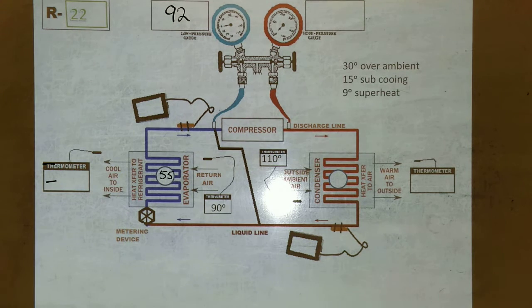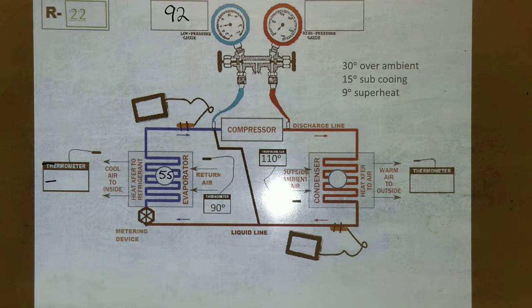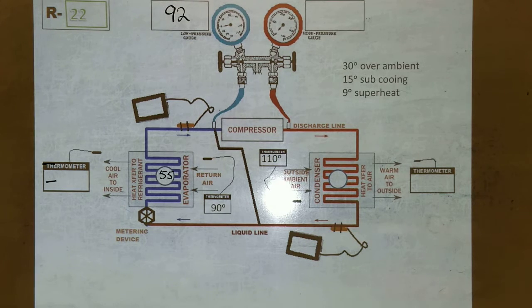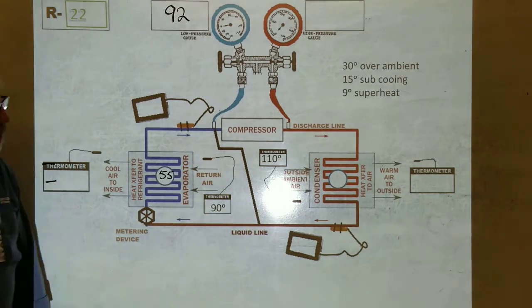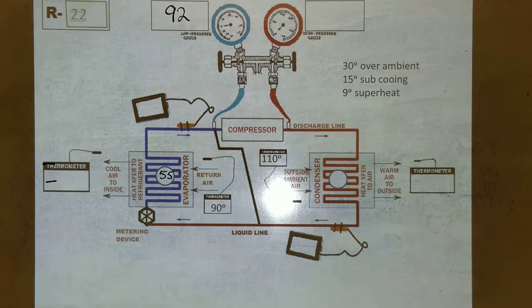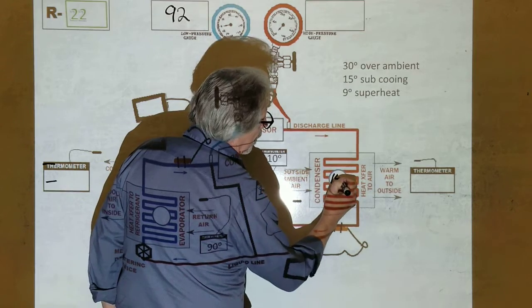So if it's 100 degrees or 110 degrees outside, you'll just enter the temperature. If it's 110 degrees outside, what surface temperature is that condenser coil? 90. 130. It's a 20-degree difference. It's either 90 or 130. That's right there, 30 degrees over ambient. Oh, 140. 140. Okay, so that surface temperature is the same thing as the saturation temperature.